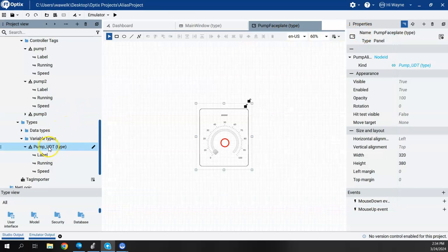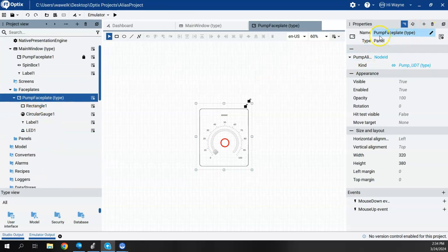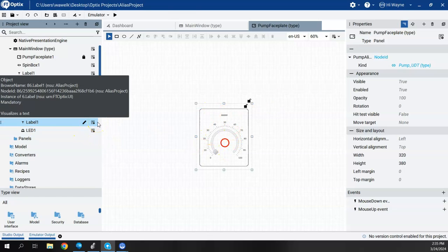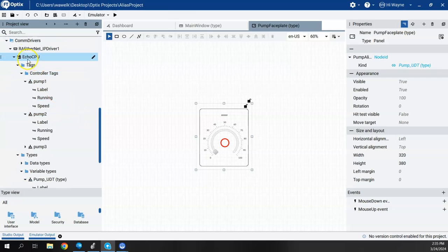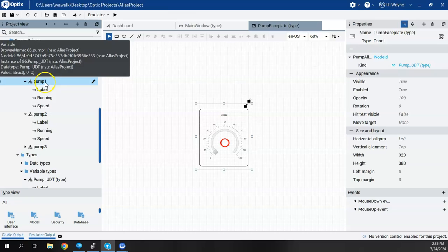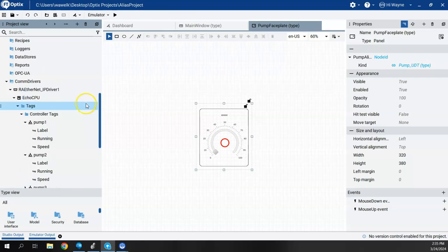All I had to do before was create this pump faceplate, create an alias for it, and then anytime I used this faceplate, I just linked it to the right instance of the pump UDT. Back down under my controller tags I had pump one, pump two, pump three. I just linked it to either pump one, two, or three instance, and all the tags — label, running, and speed — just passed right into the faceplate.